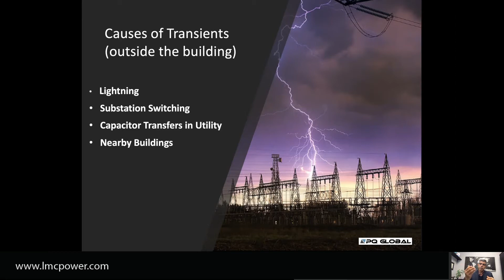Substation switching, capacitor transfers, nearby buildings like manufacturing facilities in an industrial park, equipment turning on and off, power factor correction capacitors—all of that generates transients that go back into the utility, into the substation, and then back into their building. So those are cases where we see a lot of need, and people can visually see that.